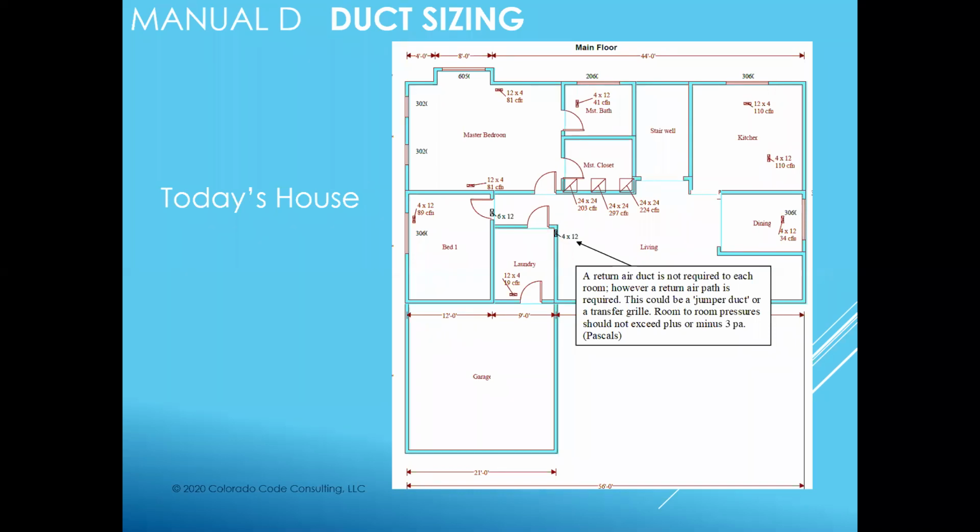Well, if somebody tells you that, email me and I'll send you the chart that says how far that's got to be cut. And believe me, if they were trying to do it in the master bedroom, they'd have a 3 or 4 inch undercut. I don't think they're going to be going for a 3 inch undercut on the door.